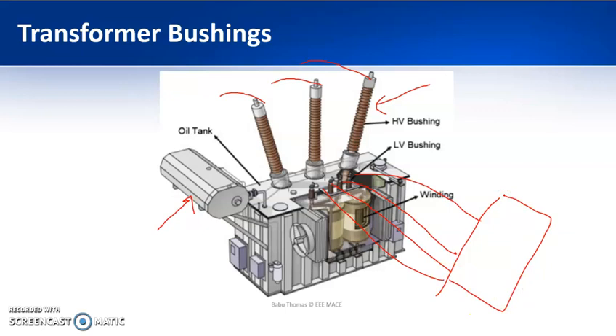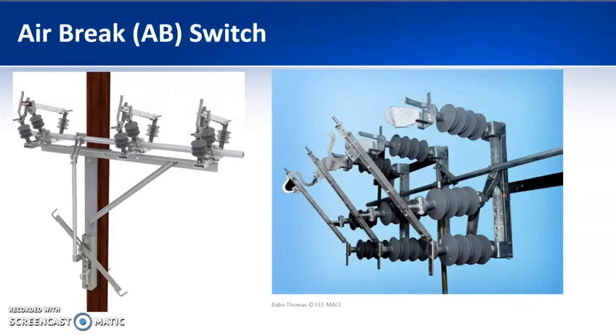Now we will see the air break switch, and this is the figure of the air break switch, a gang operated air break switch. Gang operated means you have 3 terminals for the 11 kV supply, R, Y and B, and those R, Y and B terminals are these ones, to which your supply is coming. A gang operated switch means that using a single lever you can isolate all 3 phases at the same time. Here you can see that this is the open position, and once the gang operated switch is closed, this terminal moves onto this and attaches to the system, and therefore the supply comes in line with the system.